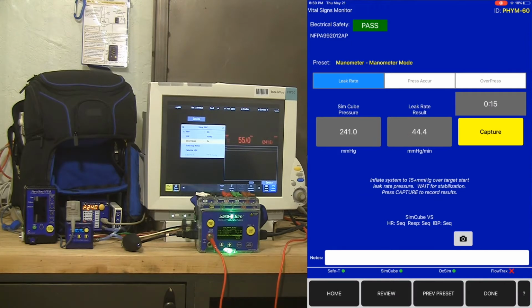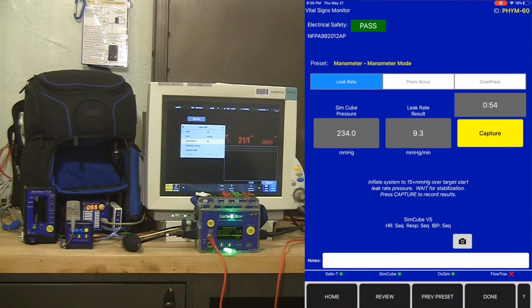We've got the SimCube pressure in that box, and we've got a timer that lets us see where the time elapsed is in the leak rate testing. So we're going to let it run for 60 seconds and make sure that we're getting a passing result, and then hit the capture button. So we're at about 53 seconds now, so I'm going to go ahead and hit capture.